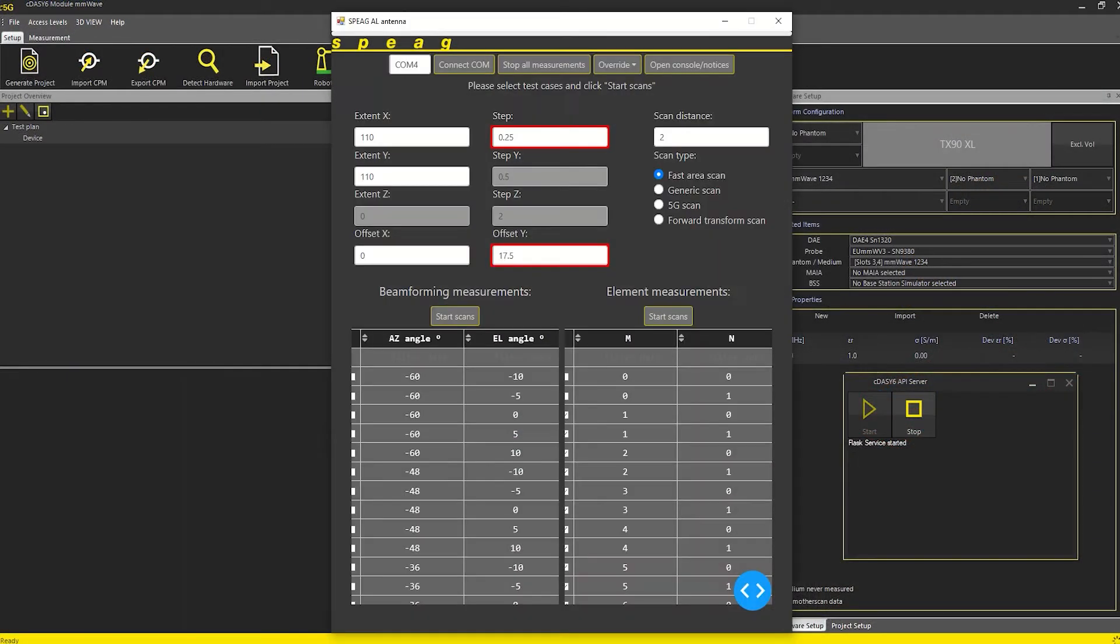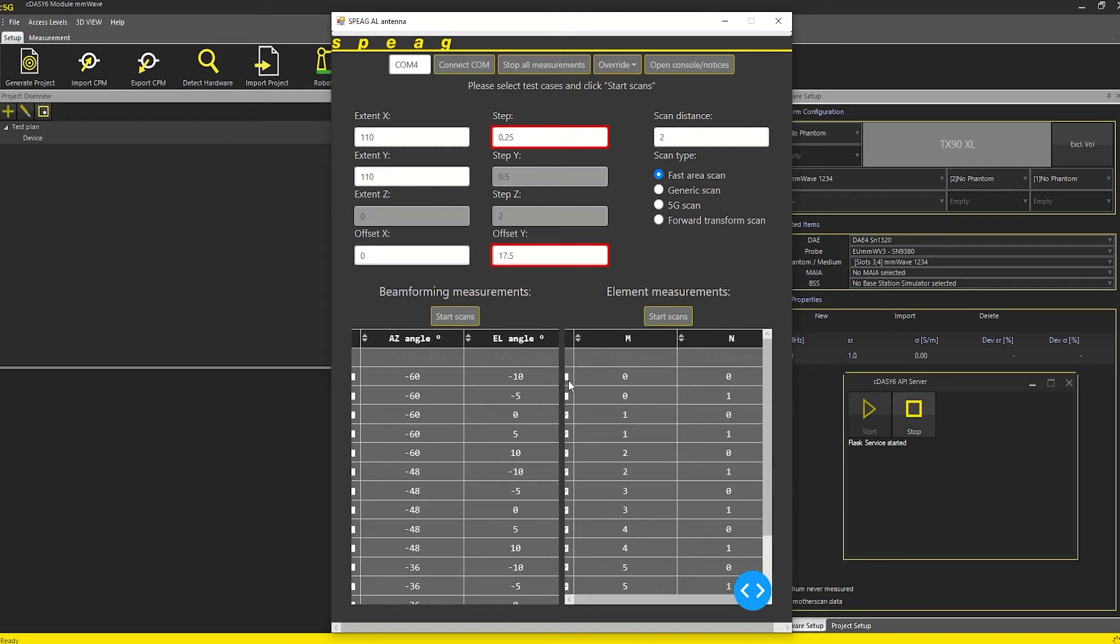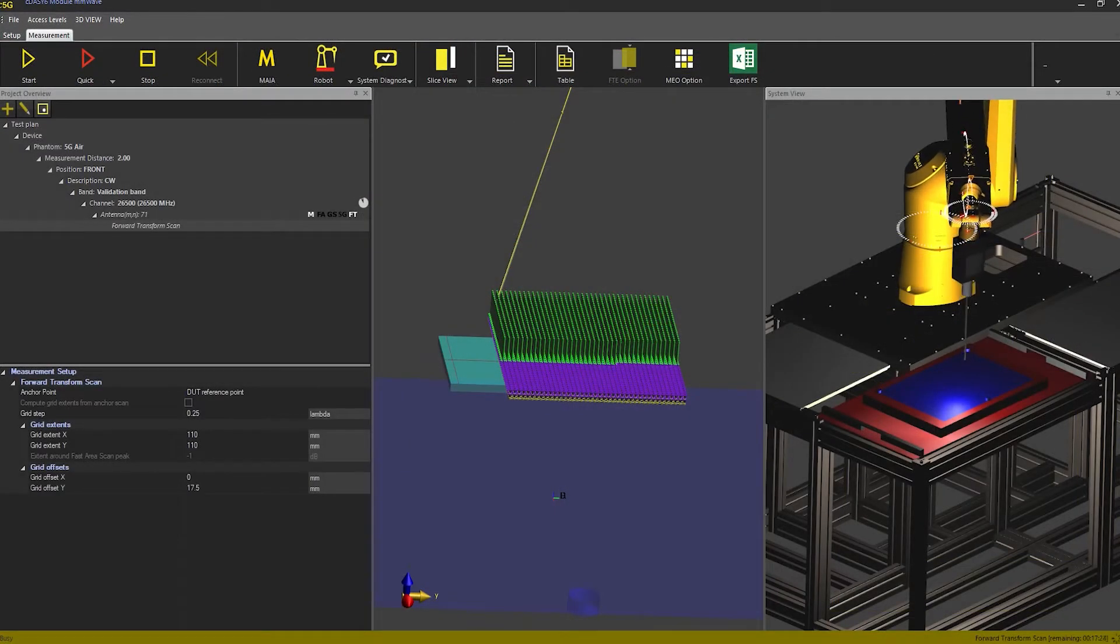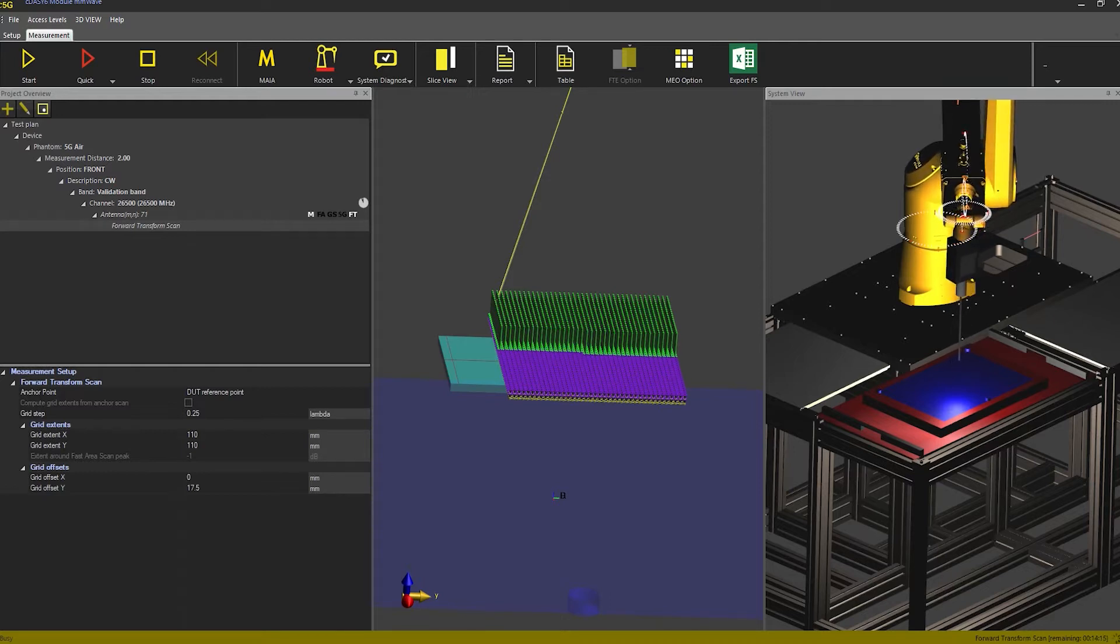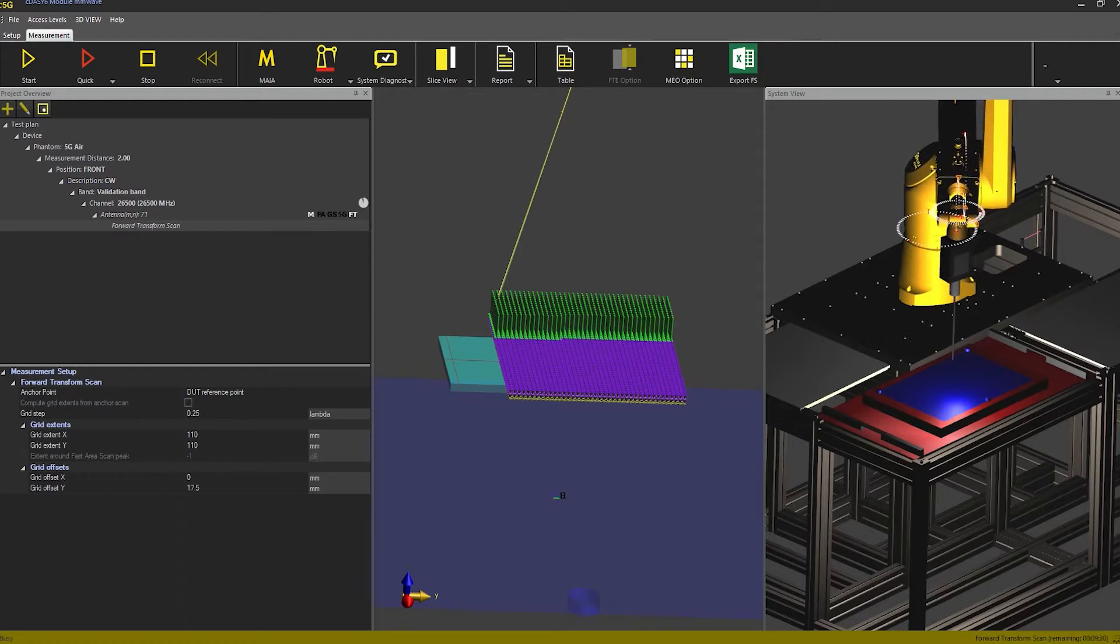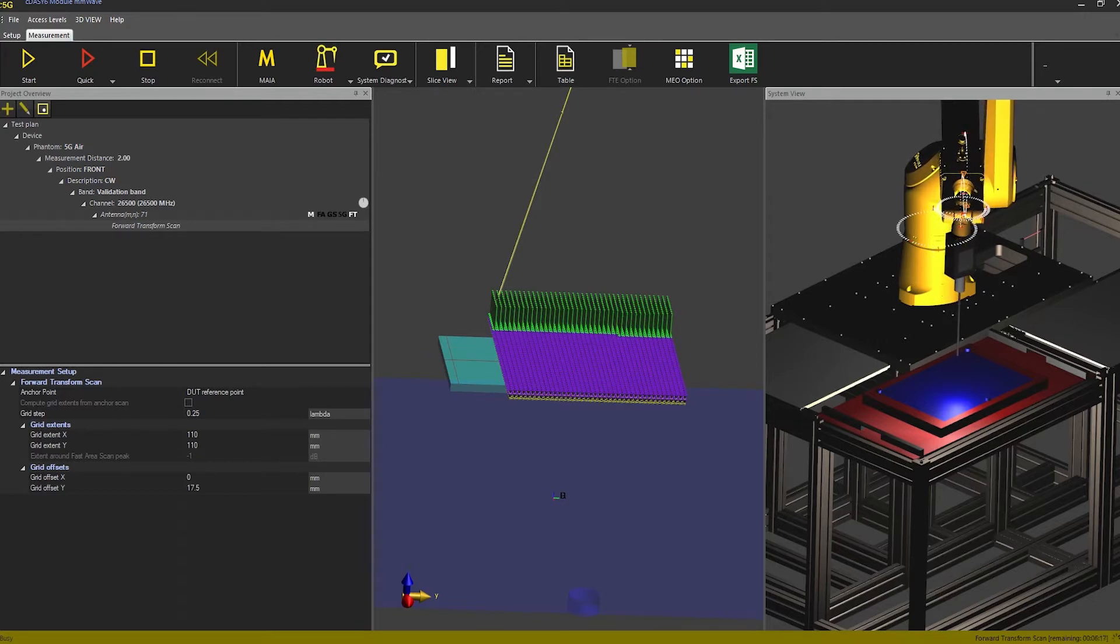The validation device is controlled via this graphical user interface which also controls the DASY6 module via the advanced application programming interface or API. The new API feature of DASY6 millimeter wave module 2.2 allows remote control of the system via HTTP commands.